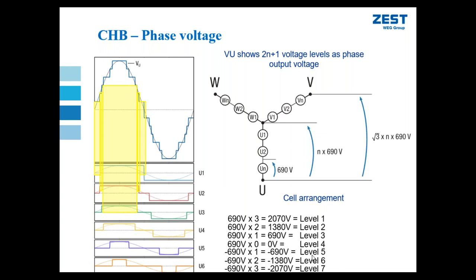I can then switch on the negative side, which is my 5, 6, and 7 levels. So that's why, if we use that formula from previously, 3 power cells times 2 is 6, plus 1 gives me 7 levels capability phase to neutral switching. And that graphically demonstrates my 7 levels there. My phase to phase voltage is essentially my phase to neutral voltage of 2070 times the square root of 3. So when I'm switching on a 3.3 kV, 3 power cell per phase drive at its maximum, it is capable of switching up to 3585 volts. That is why 3 power cells of 690 volts each are used for 3.3 kV applications.